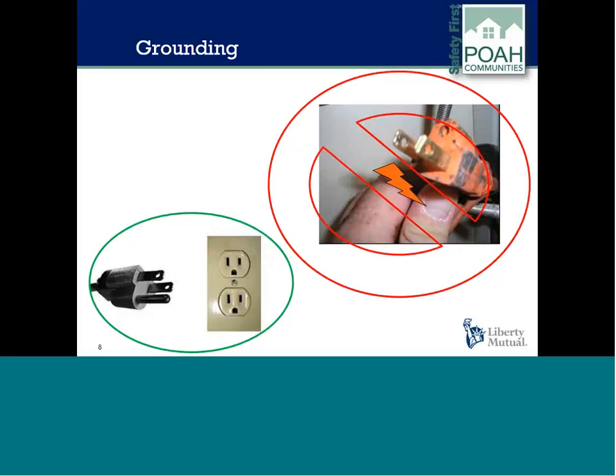Working with ungrounded hand tools can be very dangerous. Hand tools are designed to do their work, but they also can vibrate and heat up. This can eventually wear out the insulation or cause wires to break. Carrying tools by their wires can also wear out the insulation. The tool will still operate, but the tool housing can become electrically charged or hot, which can cause a serious shock or fatality. With proper grounding, the electrical current could flow through the grounding wire back to ground. If the ground prong is missing or removed and the tool's housing is hot, then you must not use this equipment.